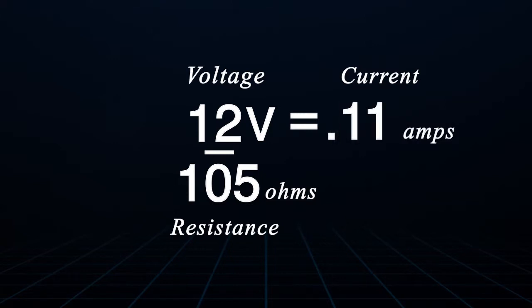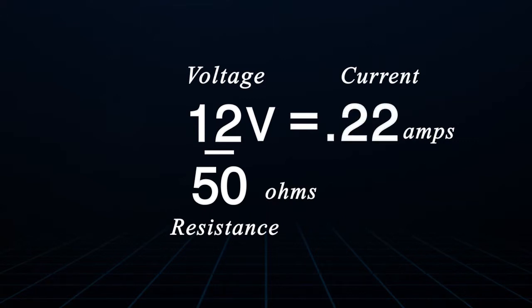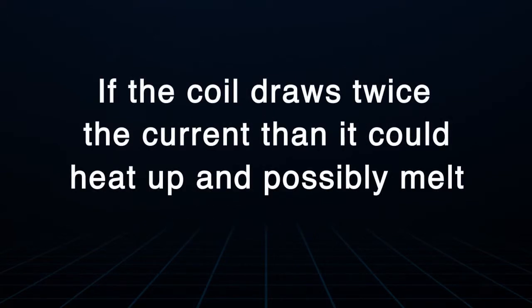If we were to test this coil and find that the resistance was 50 ohms instead of 100, that would mean it would draw twice the current that it should. If it were to draw twice the current, it could heat up and possibly melt.